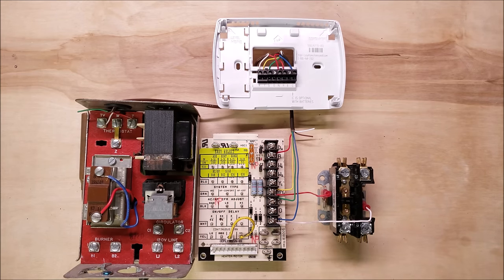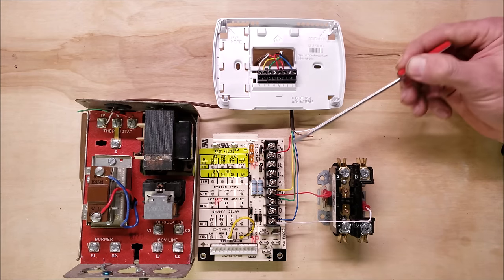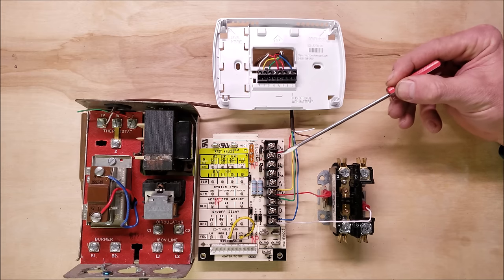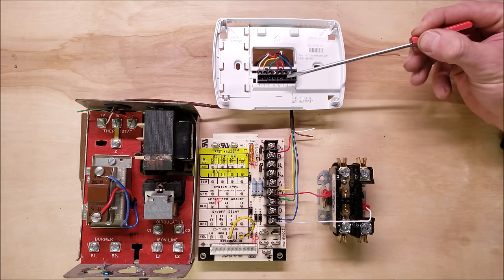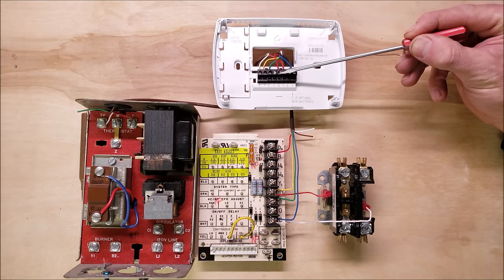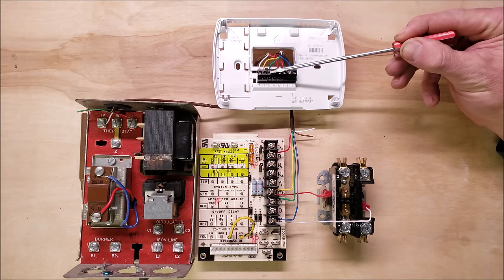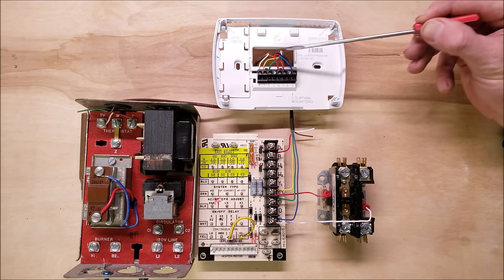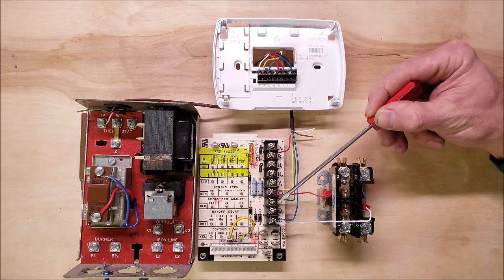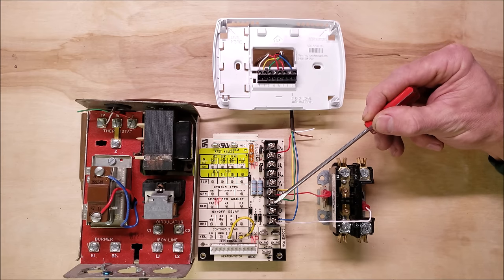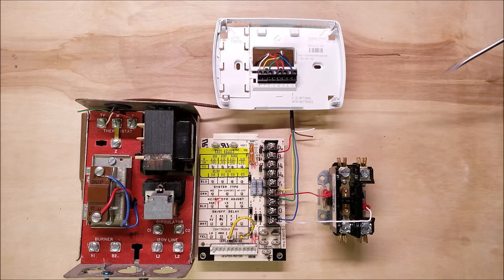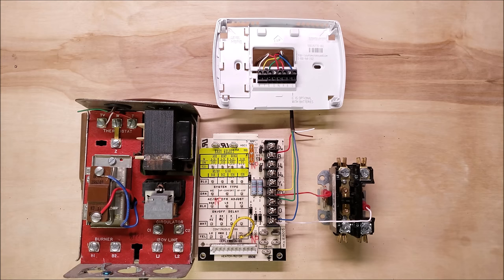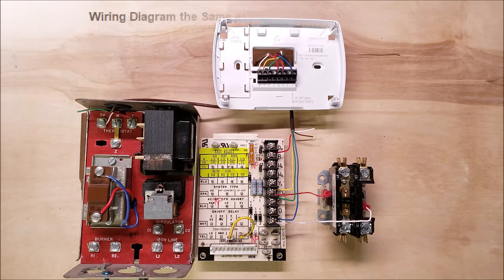If we wanted to just turn the fan on, we have our 24 volts heading in from the R to the thermostat on RC, then it connects to G and comes out of the thermostat and goes over to our G terminal on the control board. That'll turn the blower motor on. Now let's take a look at a wiring diagram that replicates the wiring right here.